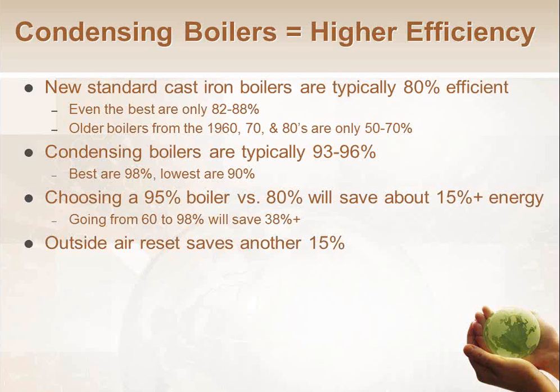So as a general rule of thumb, we take a 1% deduction penalty per year of age up to 10% maximum. So if you tell me you got a 30-year-old boiler that was 80% efficient, for my calculations, I'm going to assume it was 70%, unless you give me combustion analyzer data showing me what the real efficiency was, 77, 79, 81, whatever you really measured.